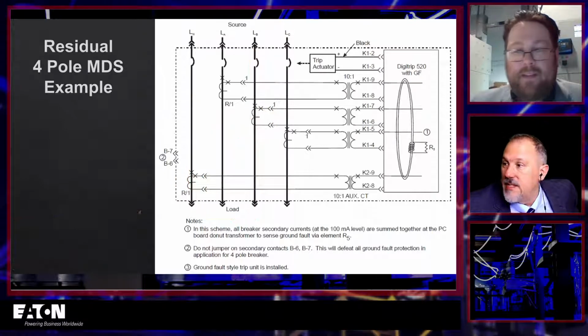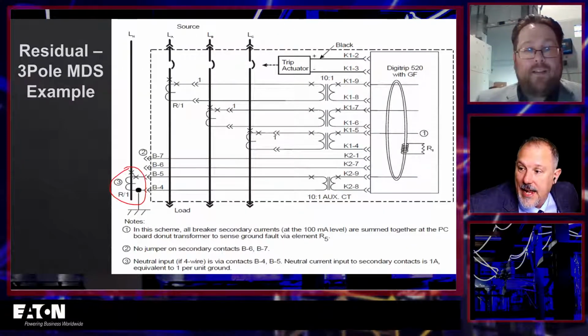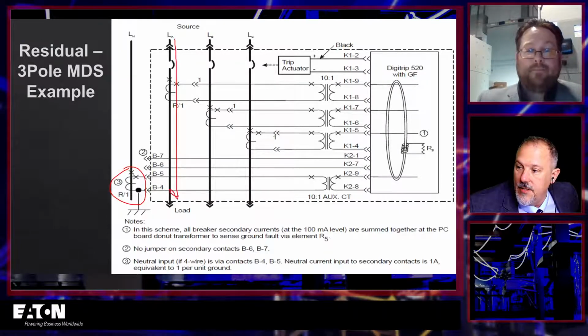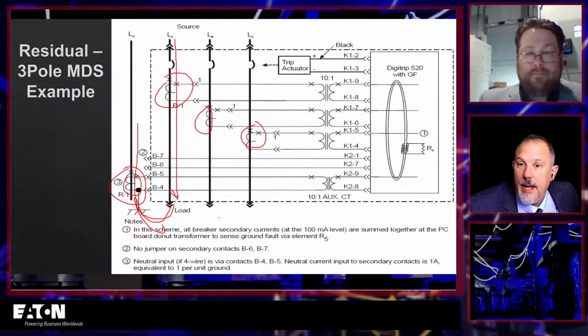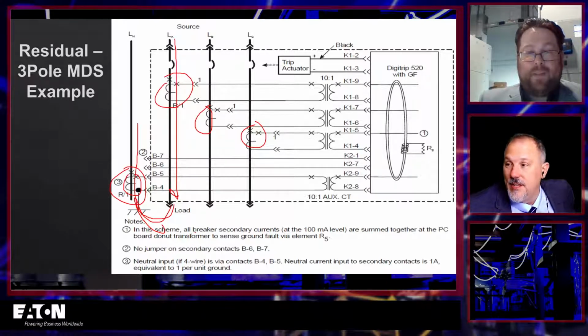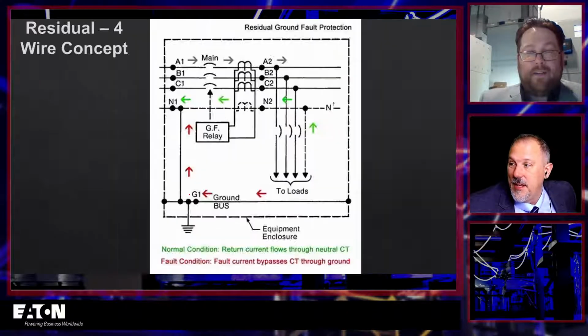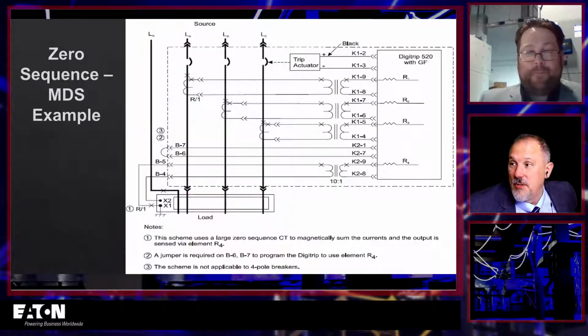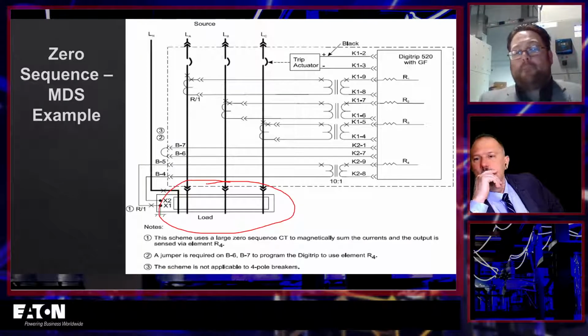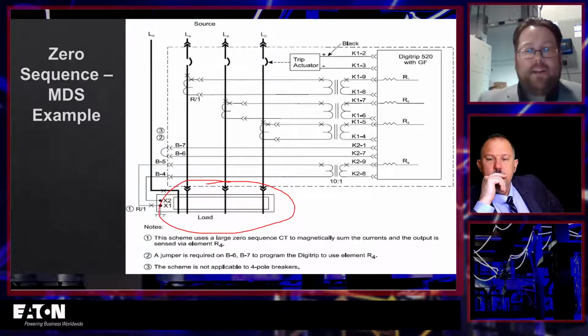And that would be the same for this. The CTs are on the outside, but you're going to inject current down this way, and you're going to put a jumper in there, and you're going to have that current come up this way. That makes sure that this CT and that CT have the right polarity. The same with this one, the same with that one, regardless of the application. You're doing the same on all of these, really, outside of the zero sequence, right?